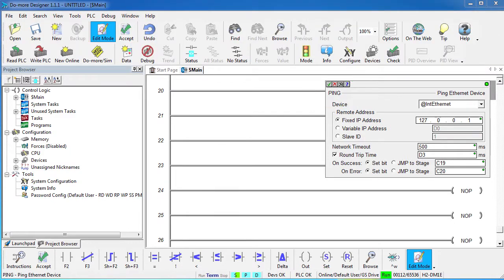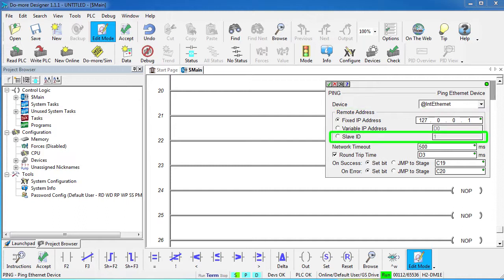The new PING instruction is awesome. You now have an instruction that allows you to verify the connection to a device in your ladder code. For IP addressing it will work with any IP device including network gateways, email servers, network printers, etc. For slave addressing it uses an HEI directed broadcast request, which means it will work with any Host Engineering Ethernet device like an ECOM100, an EBC100, a Do-more, etc., using the NetEdit ID number. That means you don't even have to have a valid IP address in the devices to find them. That's great for debugging network issues, and now you can display the status of your network devices on an HMI from your ladder code. And you can even measure the round trip time to that device.